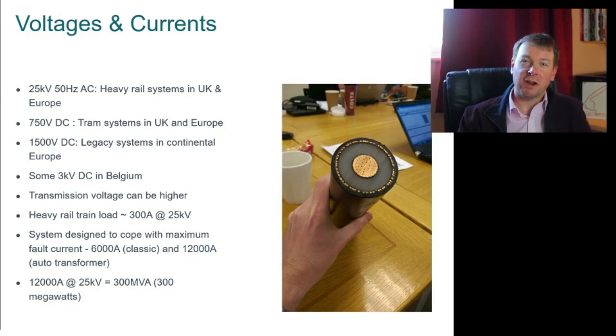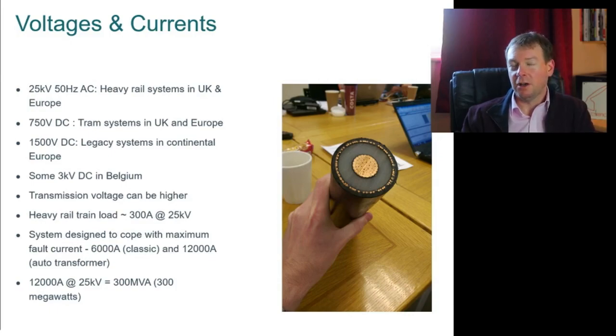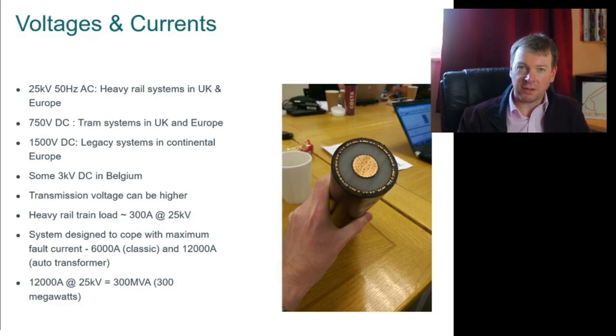But that's not really the current that people like me, line engineers, worry about. It's not the normal operation current, it's the fault current. It's the current you see when something goes wrong and current starts to flow into a short circuit. Under those circumstances, we'll typically see currents of up to 6,000 or even 12,000 amps. So that's a very significant amount of energy. 12,000 amps at 25,000 volts is 300 megawatts of power. So that's a lot of power.